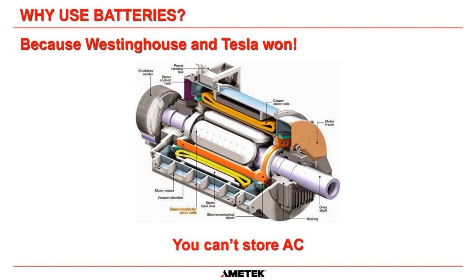So we have to have batteries because the grid is good, but there's always going to be outages. And Texas was a perfect example of that when we had the freeze, was it January, February of this year? We had a huge amount of power outages. So that is why batteries are used: to store power when the power is good. And then when the power goes out, the battery supplies that power to your load circuits, so you can shut them down in a controlled manner, or you can ride out the outage until the power comes back on again.